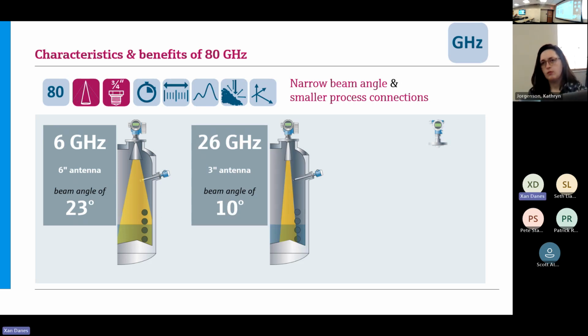Now if we increase the frequency and look at something in that 26 gigahertz range, I don't need a 6-inch antenna. With a 3-inch antenna, my beam angle's down to 10 degrees. So I don't need as large an antenna to get that signal down into the tank. I'm able to get quite a bit more focusing without having to stick what looks like a boat motor inside the vessel.